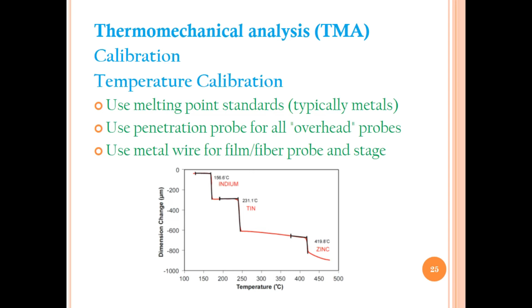The calibration continues. The last one is the cell constant. Cell constant is also an important factor in TMA instruments. Cell constant calibration will improve accuracy but not the reproducibility. Reproducibility is the analysis of the same material by different labs, by different chemists. This is called reproducibility. The calculated cell constant should be 1 plus or minus 0.05. Cell constant calibration should be used when the highest accuracy is required. Highest accuracy is less than 2%. Accuracy is basically the difference between actual results and the true results.